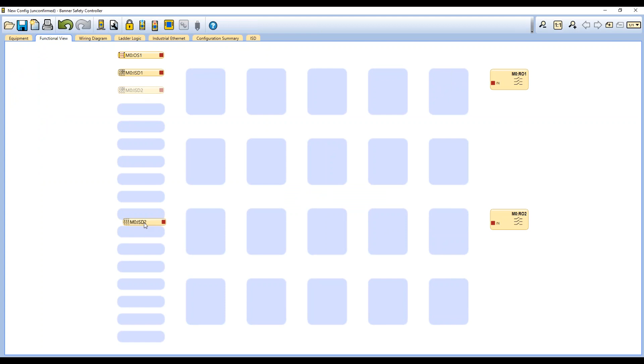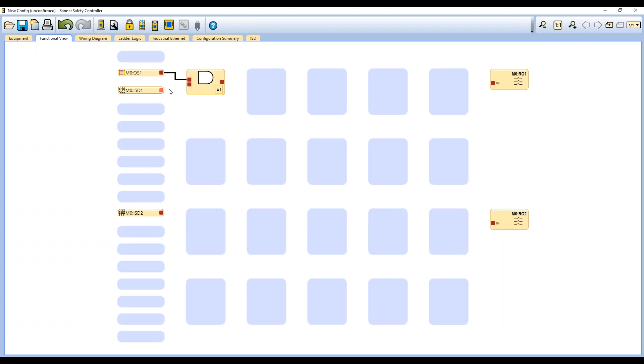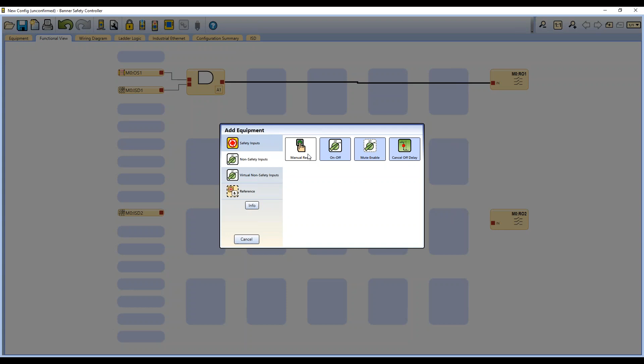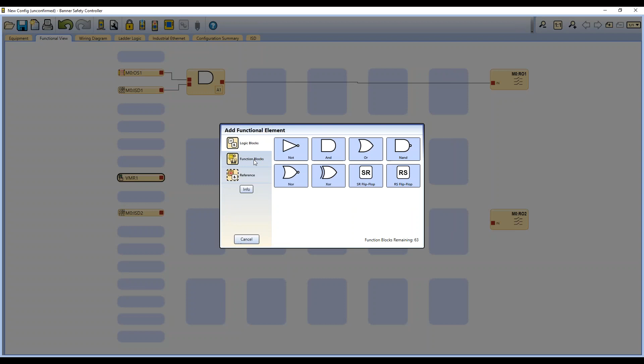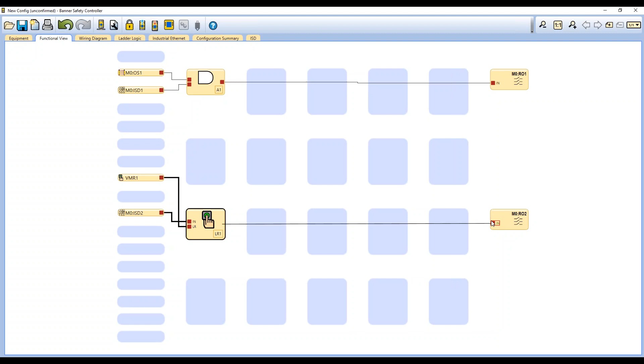You add your devices and can drag and drop things in this view. I did an AND gate for these 2 devices, so if the door switches or light curtains trip, it'll trigger channel 1. For the E-stops, in my demo kit I had an actual wired reset, but you can do a virtual manual reset - just select that, run it into a reset block, connect those things to the output, and my system is done.